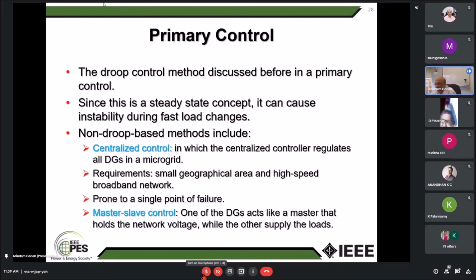And I can do a very fast load flow, and I can schedule all my generators, and I know the apparent impedance of the lines, etc. So I can actually do a centralized control without any problem at all. But the requirements are a small geographical area and a very high speed network, which is possible if it is a small geographical area. Now, what's the problem? You have a single point of failure. If the communication network breaks somewhere, then the DGs don't know what to do, and there will be a total catastrophe.